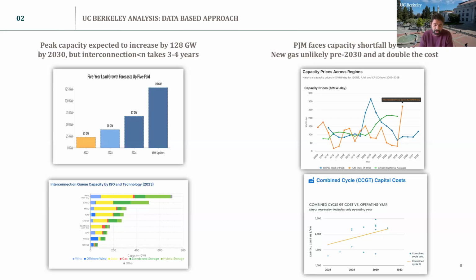In addition to interconnection issues, there are significant supply chain challenges, especially for gas power plants. Today it takes around 3 to 4 years to procure a gas turbine. Combine this with supply chain issues in transformers and the interconnection issues, and we estimate that any new gas plant ordered today would not come online before 2031 or 2032. The result is a real possibility of capacity shortfall in the coming years.